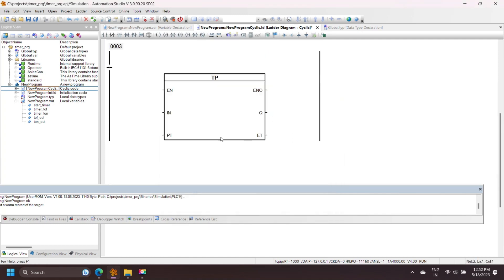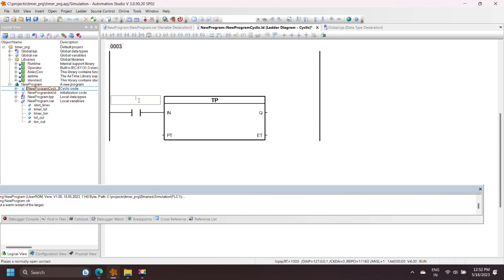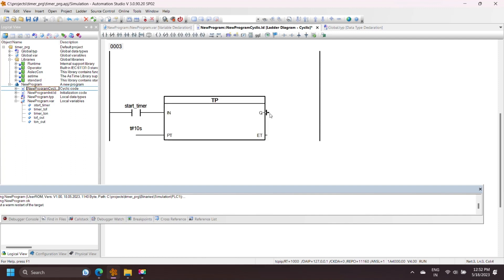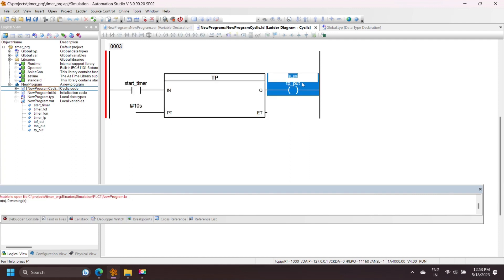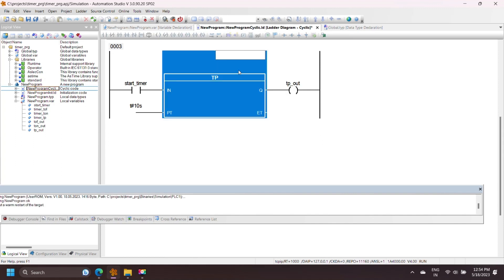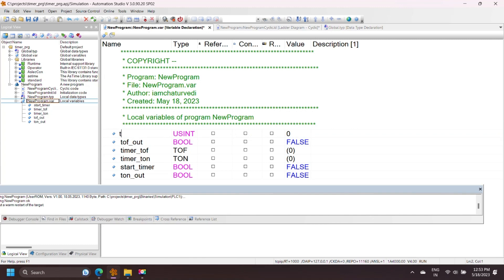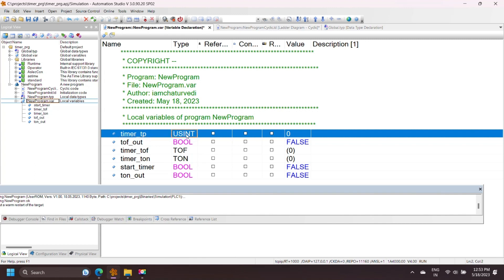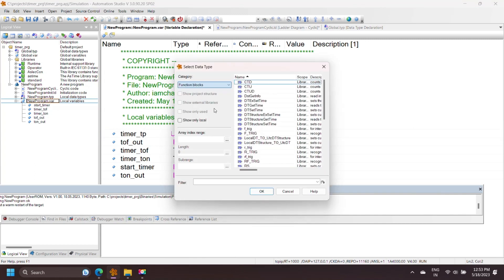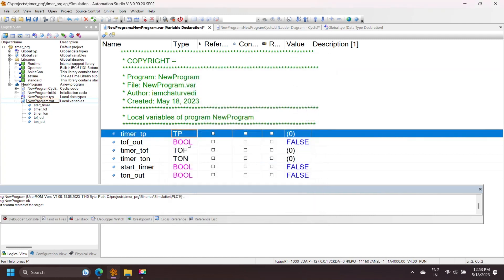The pulse timer (TP) on a rising edge of the timer input bit increases an internal timer up to a given preset value. Any change to the timer input bit during timer operation has no effect. If the timer elapsed value equals the preset value, the internal timer is reset. Declare variables for the pulse timer — the instance name is TP, input and output are bool data type, and preset and elapsed times are time data type.